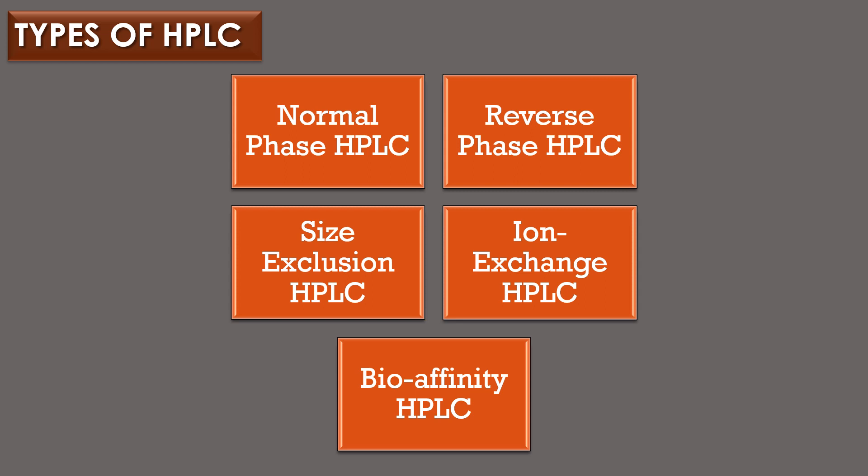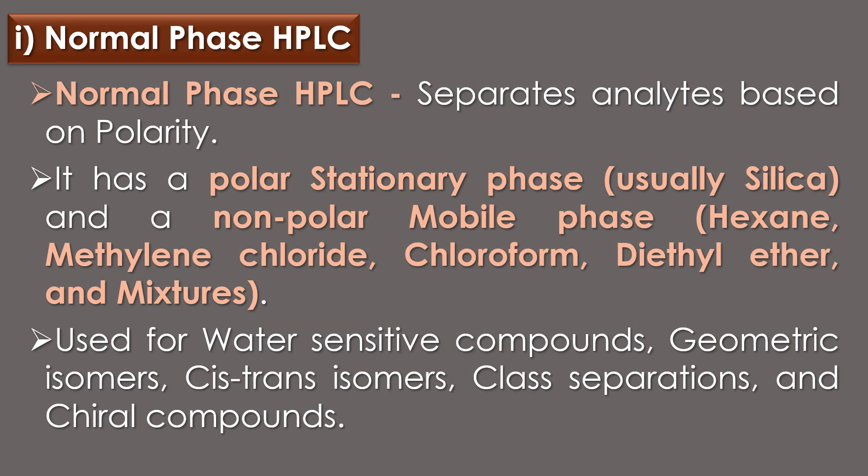There are five types of HPLC: normal phase HPLC, reverse phase HPLC, size exclusion HPLC, ion exchange HPLC, and bio affinity HPLC. Normal phase HPLC separates the analytes based on polarity. It has a polar stationary phase, usually silica, and non-polar mobile phases like hexane, methylene chloride, chloroform, diethyl ether, and mixes of solvents. The normal phase HPLC technique is used for water-sensitive compounds, geometric isomers, cis-trans isomers, class separations, and chiral compounds.